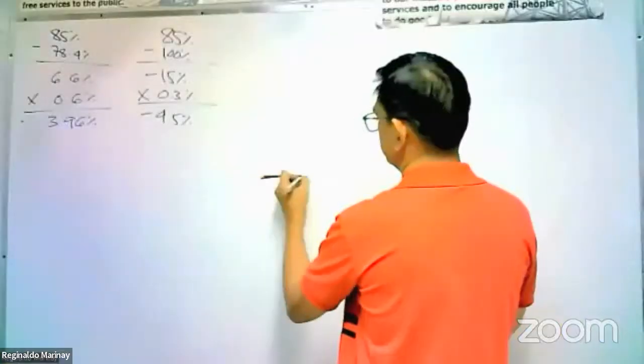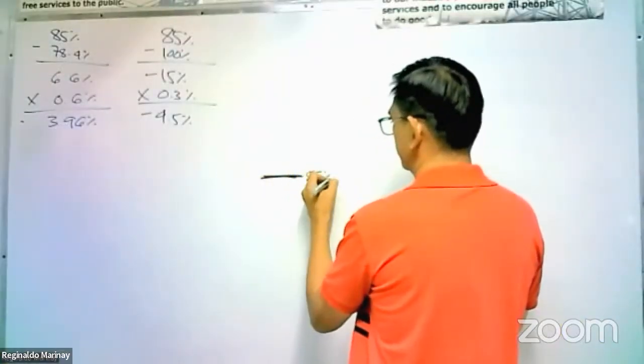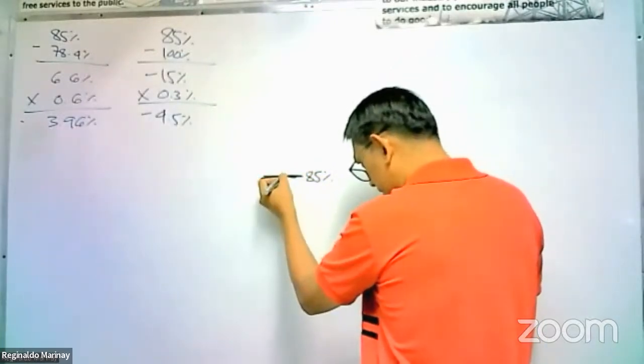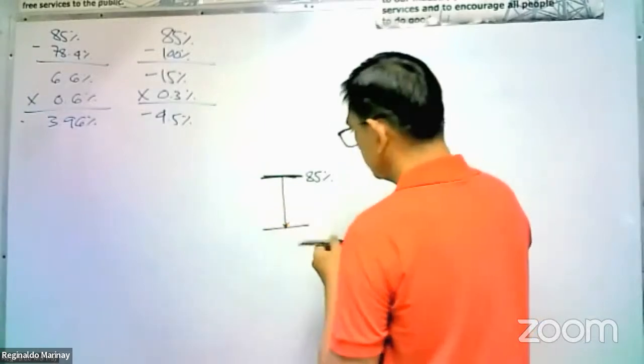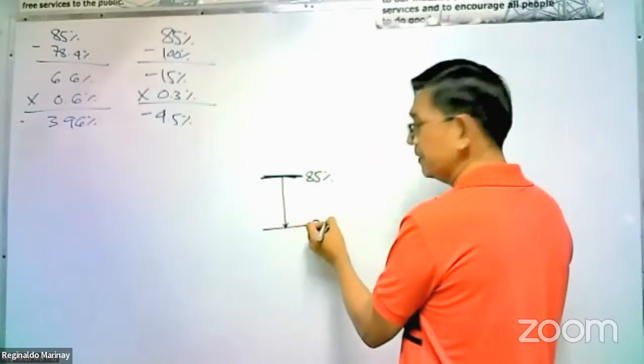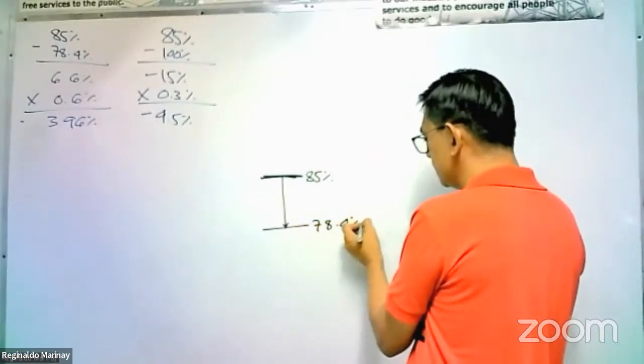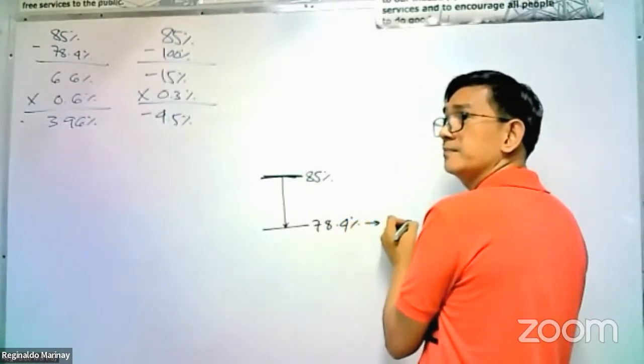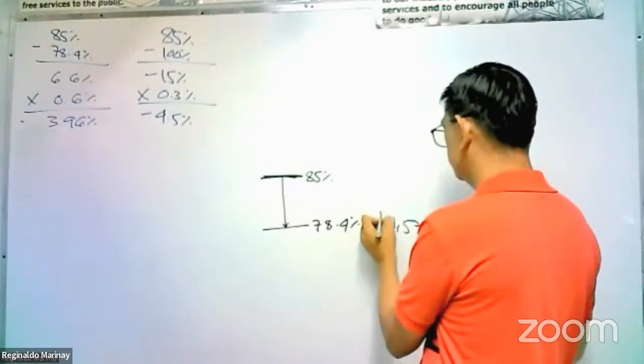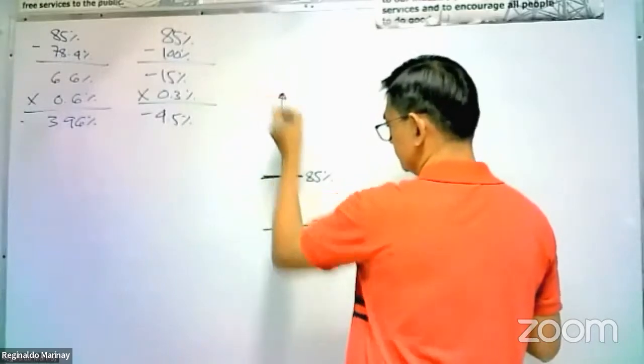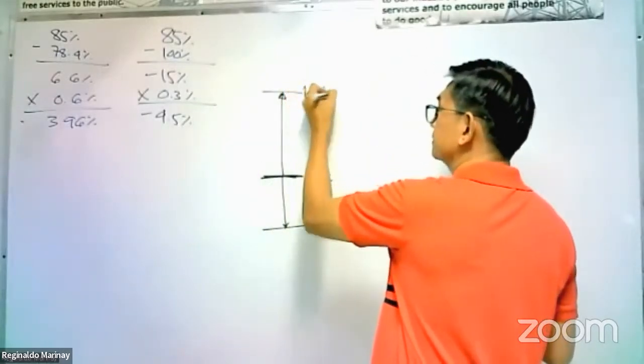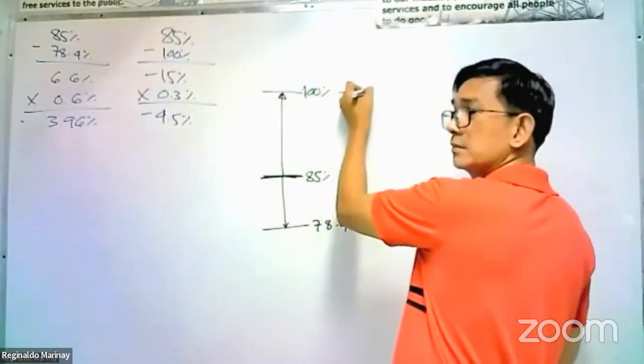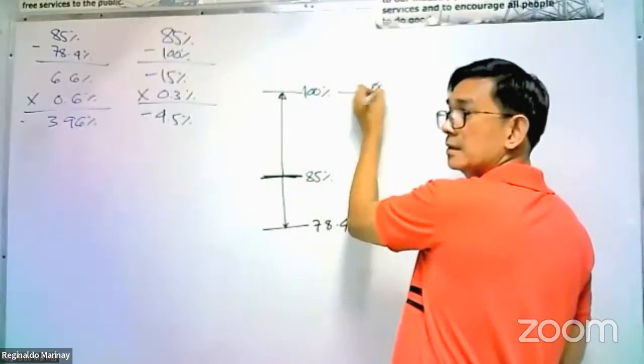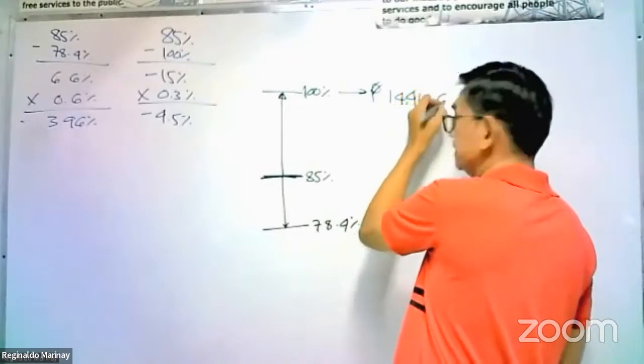So let us have this illustration. You have 85% power factor base here. So when you lower the power factor, you come up with a penalty. Let's say it drops to 78.4%, and that is a penalty amounting to 11,578.7 pesos. But when you increase the power factor to 100%, you come up with a discount of 14,412.6 pesos.